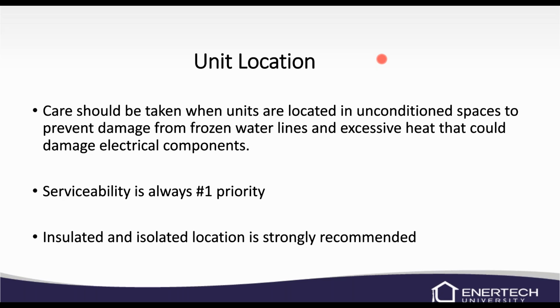The best would be distance around the entire unit. That's not feasible in a lot of situations. So you have to get to the front of the unit. We got water lines coming out the back of the unit, and we need at least one side to access the refrigerant components. So you're going to need a good area there, 2-foot distance around the unit, so you can work on it.